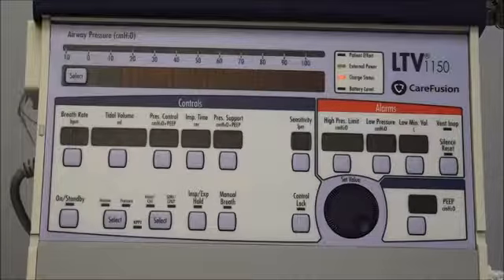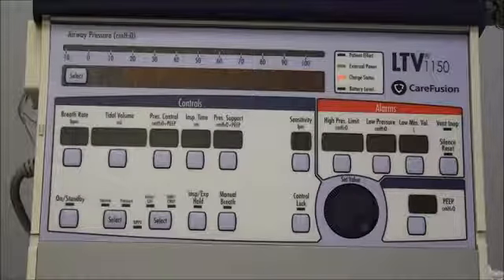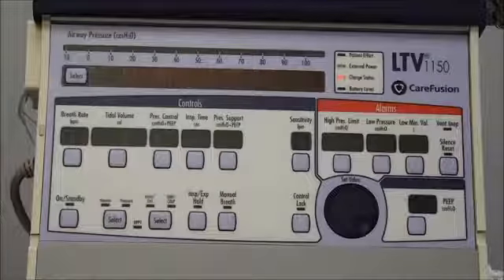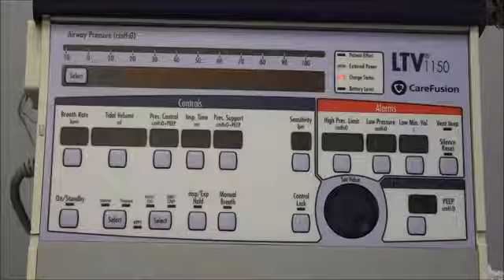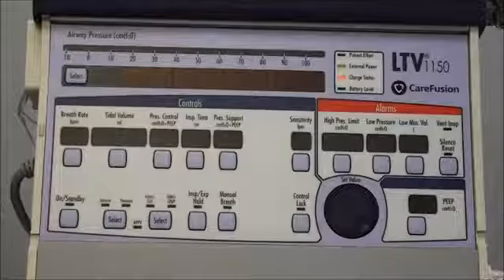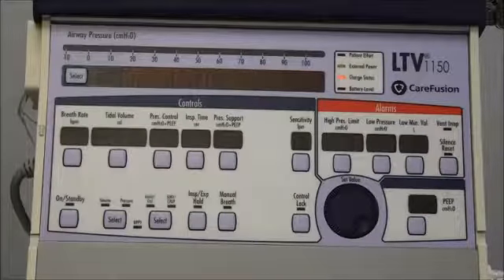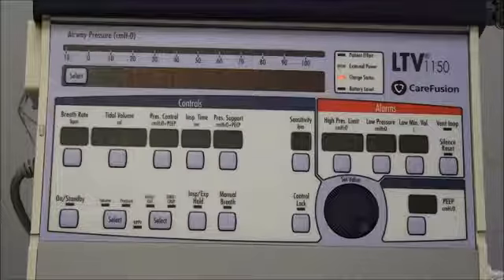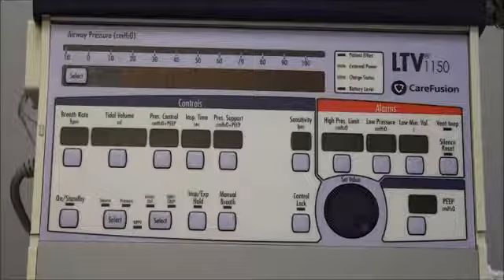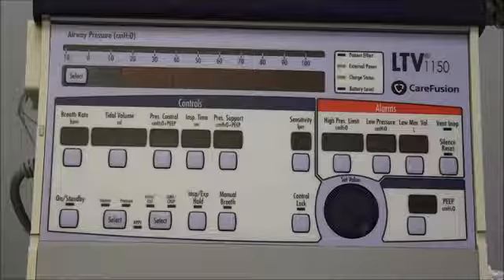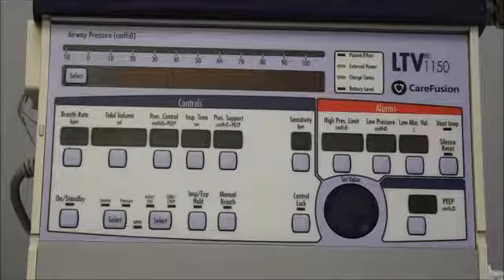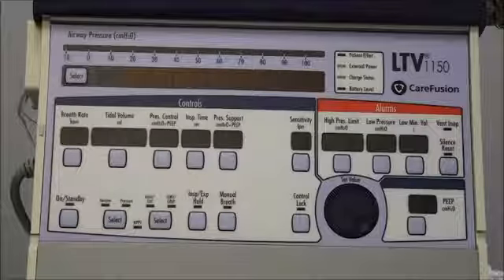So the charge status is going to tell you when that internal battery is being charged, and it will either be green, amber, or red. Green will tell you that it's charged, amber will tell you that it's charging, and red will tell you that it needs to be charged. The battery level light will also tell you what level the battery is at. And when you're using it on the battery, that's when you'll see that light illuminate. So if you have a lot of time left on your battery, it'll be green. If it's starting to get lower, it'll be amber, and when it needs to plug in and be charged up, it'll go to red.